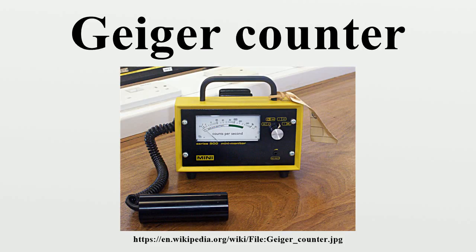In wide and prominent use as a handheld radiation survey instrument, it is perhaps one of the world's best-known radiation detection instruments. The original detection principle was discovered in 1908. But it was not until the development of the Geiger-Müller tube in 1928 that the Geiger-Müller counter became a practical instrument. Since then it has been very popular due to its robust sensing element and relatively low cost. However, there are limitations in measuring high radiation rates and the energy of incident radiation.